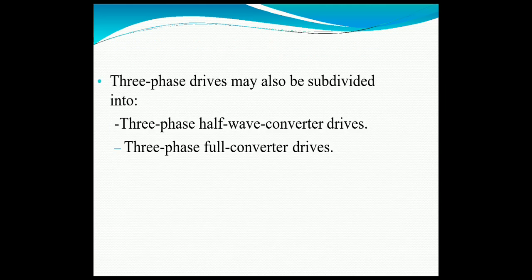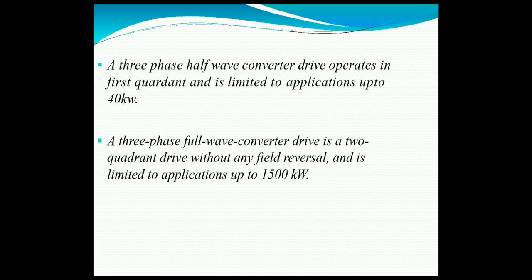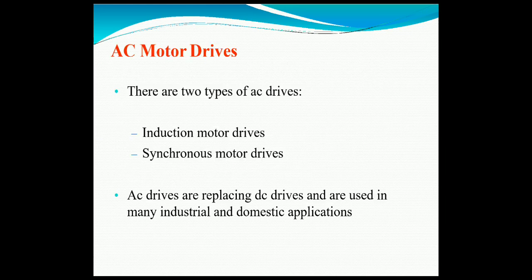The three-phase drive may also be subdivided into three-phase half converter drives and three-phase full converter drives. The three-phase half converter drive operates in the first quadrant and is limited to applications up to 40 kilowatts. The three-phase full-wave converter drive is a two-quadrant drive and is limited up to 1500 kilowatts.